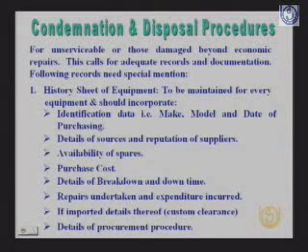For this, it will be very efficient if we develop a history sheet. A history sheet of the equipment is a very important document which must be maintained, especially for costly equipments like X-ray machines, laboratory equipments and ventilators.